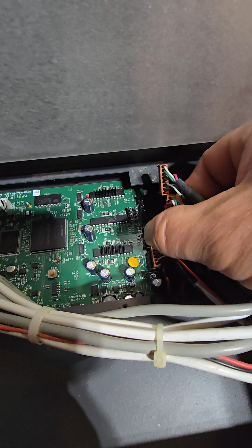Over this side. This one over here can be a little stubborn. And the one over here, not so bad. And then finally, you also have a little connector over here. And you remove that as well. That's a little pressure sensor for the air assist on the system. So you've got to kind of squeeze the connector and pick it up out of there. That also can be, for some reason, stubborn on some systems.